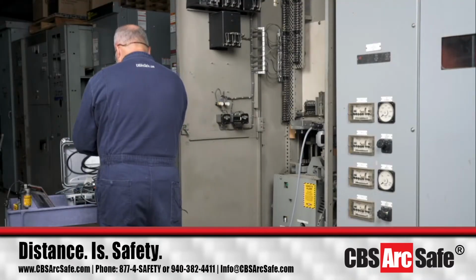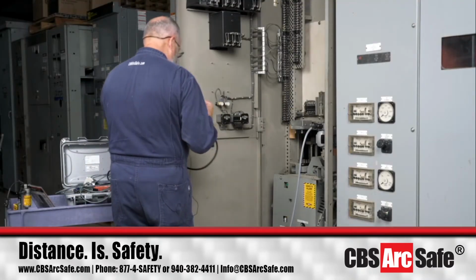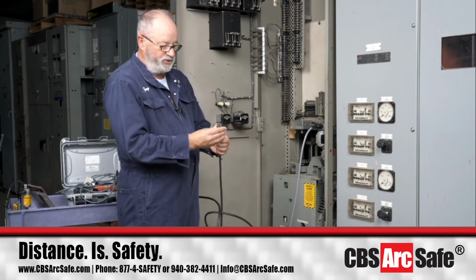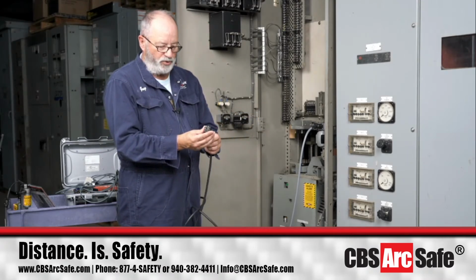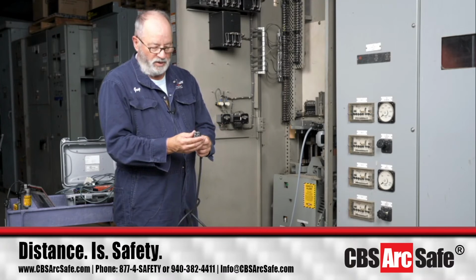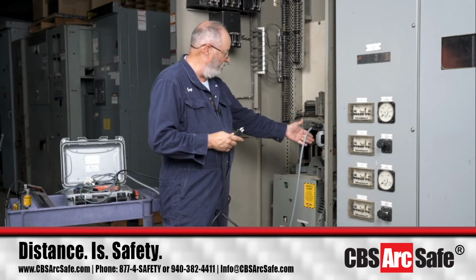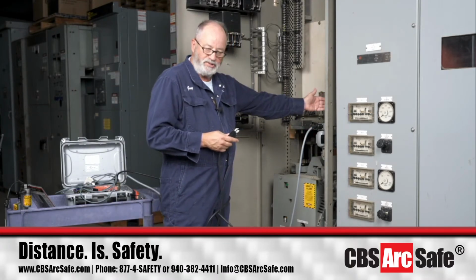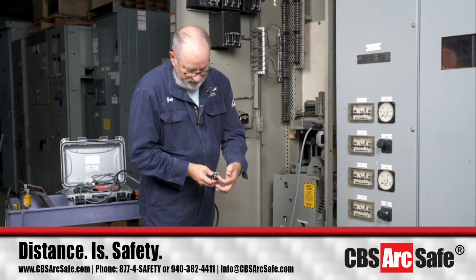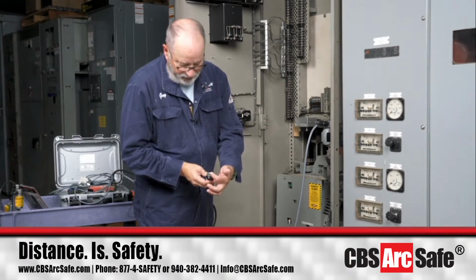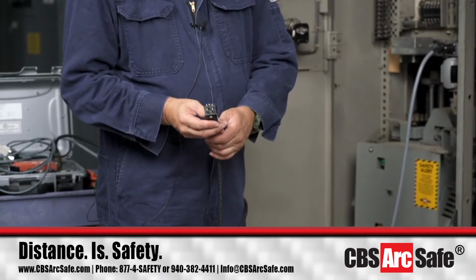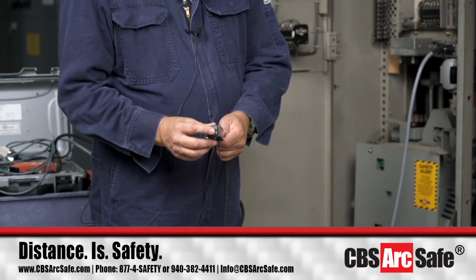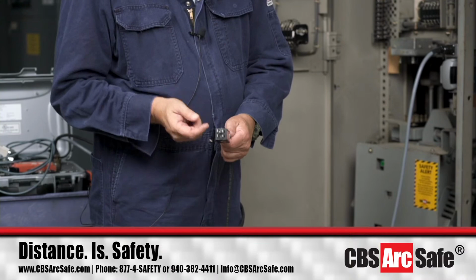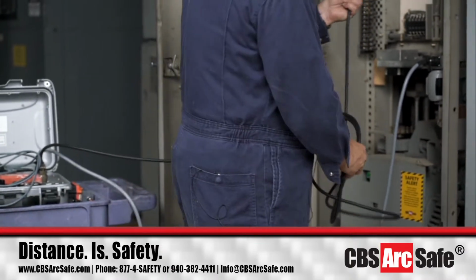Next, we're going to put in the supervisory link. This is the standard General Electric plug, which the motor would normally have on itself. If it was a regular standard GE clip-in motor, it would go from here up to the socket there. You can see the part in the middle of the neutral is slightly high, so you could try to screw this up, but it's only made to go in with this in the upper position. So we're going to go ahead and plug that in here.